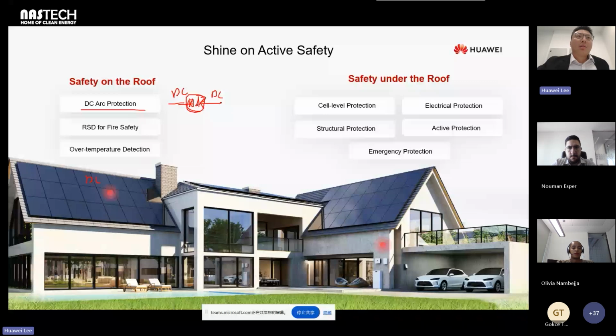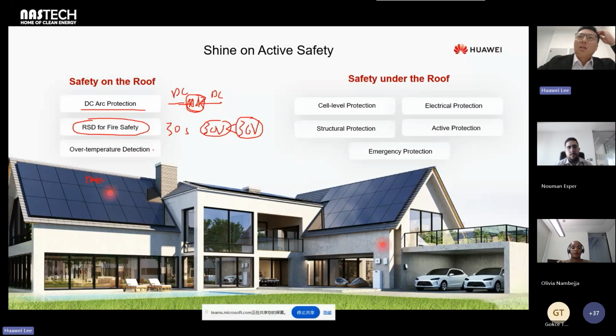And next is RSD for fire safety. In some countries there are standards for rapid shutdown: within 30 seconds, less than 30 volts. The 30 volts is less than the human body safe voltage of 36 volts. The firefighter can put water on the roof and put out the fire. And next is over temperature detection for the optimizer input and output terminals. And next is safety under the roof.